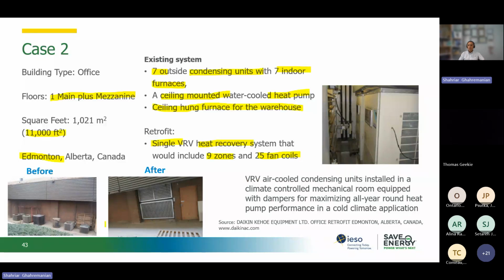So you see these condensing units outside. But as I said, it's better to consider, if we have space inside the mechanical room, bringing the outdoor unit inside our building, because the VRF or heat pumps become more efficient. What they did was add grills to bring air to the system, and basically a 20-ton system made up of two 10-ton VRF system modules. So these are the two units that they installed inside the building. And then that's it. Basically, they added dampers to the wall of the mechanical room. And this system works perfectly in Edmonton, which has a colder climate than, for example, the GTA in our case.